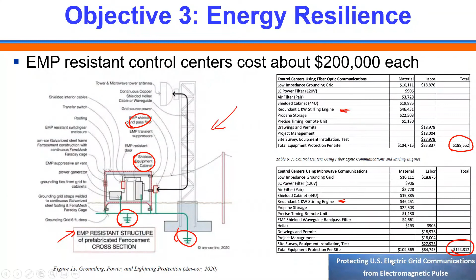In this case, they show estimated costs using Stirling engines, but they all fall around $200,000 per substation. And the substations and control rooms and all those things, as I mentioned, would have to be designed for EMP shielding with a variety of modified cable points of entry to prevent an induced current from entering into the building and doing damage to all of the controls equipment within that building.